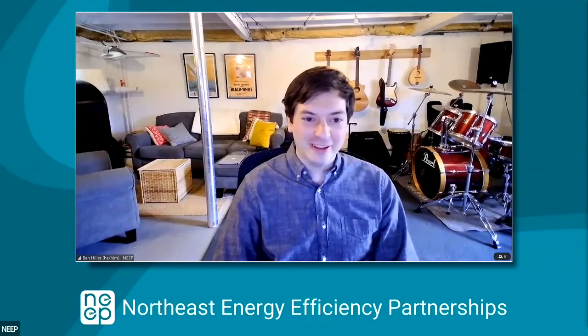As Steve mentioned, I'd venture to guess that more than 50% of our existing commercial building stock uses air to cool and, by and large, heat. But you can actually use a VRF system to retrofit a unit like that. For example, a rooftop unit providing air conditioning can be retrofitted with a refrigerant coil from a VRF system. That's a really quick and effective way to convert a gas-fired DX air handler into something more efficient in heating and cooling that doesn't burn fossil fuels. It's an interesting conversion approach.